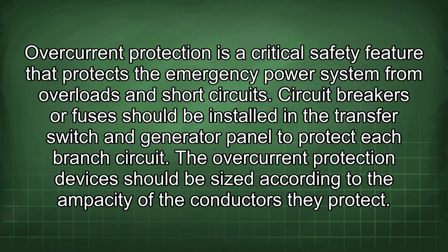Overcurrent protection is a critical safety feature that protects the emergency power system from overloads and short circuits. Circuit breakers or fuses should be installed in the transfer switch and generator panel to protect each branch circuit. The overcurrent protection devices should be sized according to the ampacity of the conductors they protect.